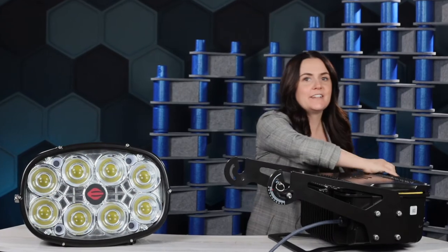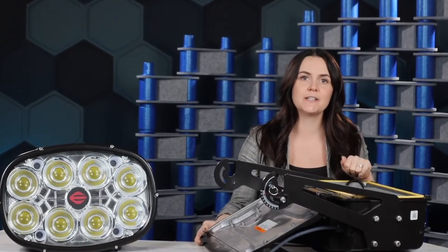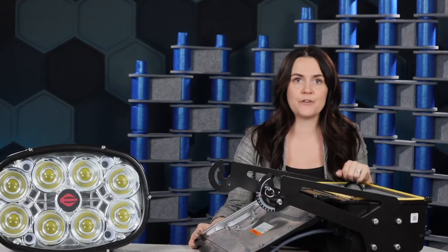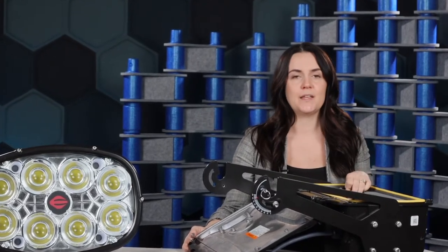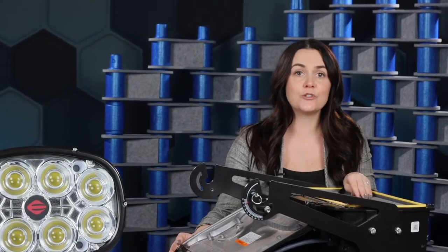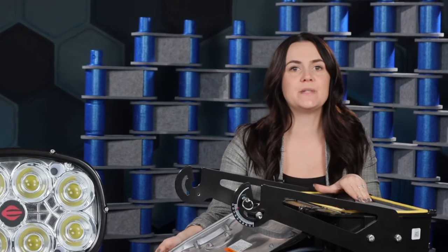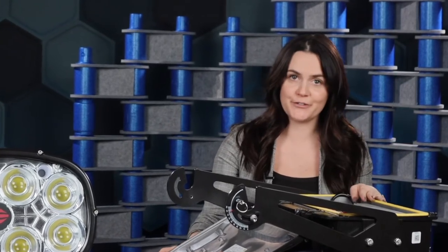This box contains dual drivers with added internal surge protection to ensure your field stays illuminated for the total lifetime of the system. This redundancy of power virtually eliminates maintenance, as a single driver failure will not require a trip out to the site. Both drivers will need to fail before you would ever see an effect on the field, which means nobody's going to be stealing third in the dark.